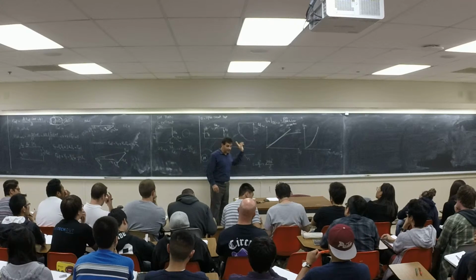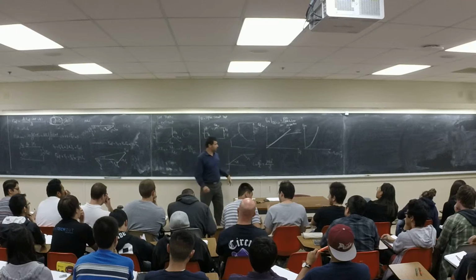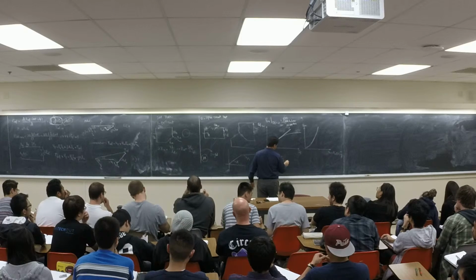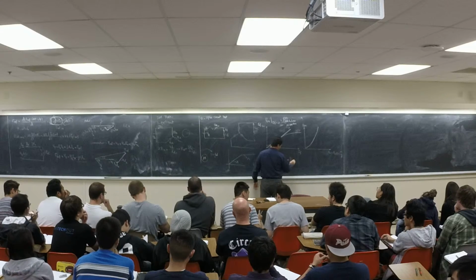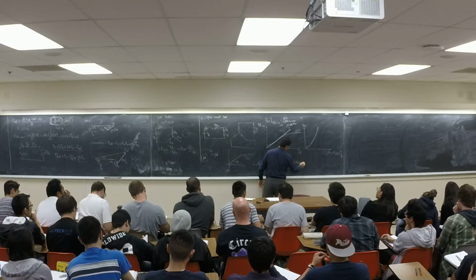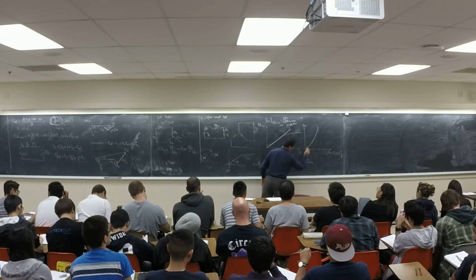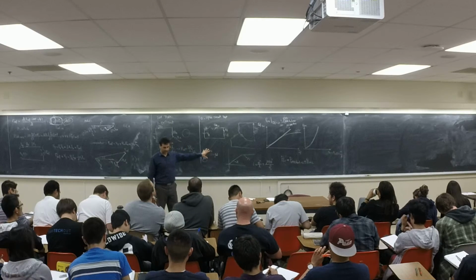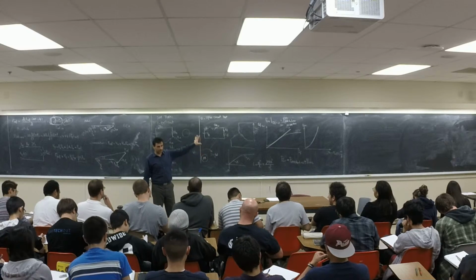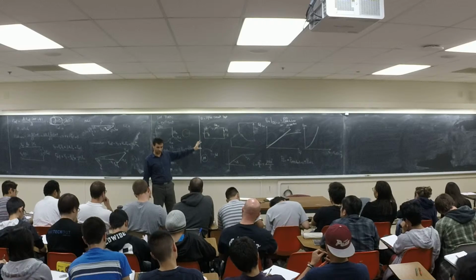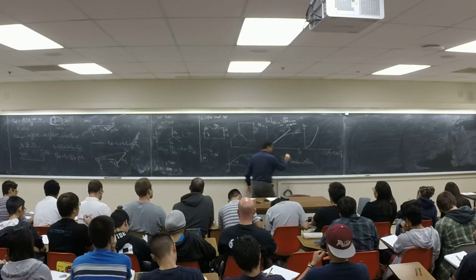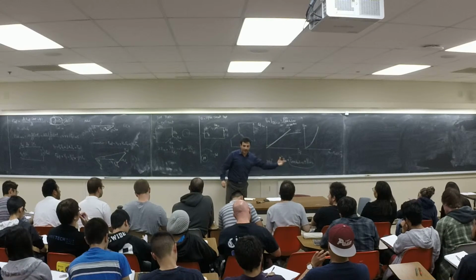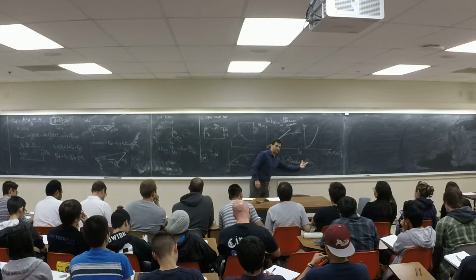And if you measure the power now, the POC, let's call it here, I call it POC at IF. POC is going to be P mech loss plus P core, right? When we have the excitation system. So if you do it at synchronous speed and nominal voltage, you have these two together. You measure these two together.